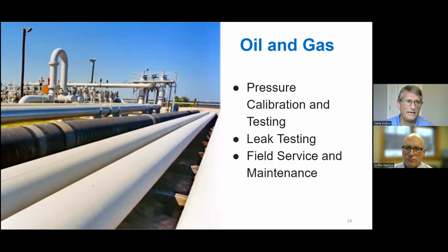There are several applications for quick test in oil and gas industry. Quick test system is ideal for calibrating pressure instruments used in oil and gas production, refining, and transmission. For pipeline and valves, the quick test system can be used for high accuracy leak testing, ensuring system integrity and environmental compliance. The portability of the quick test system makes it ideal for field technicians who perform on-site calibration and diagnostics.